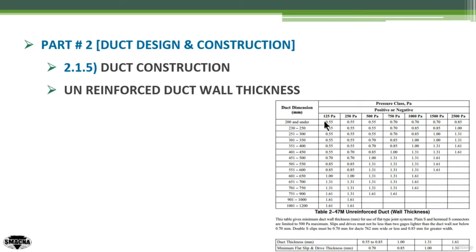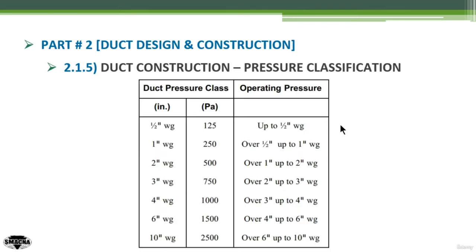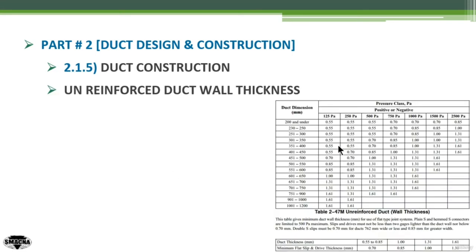The duct pressure classification depends on the external static pressure (ESP) of the fan. For example, a fan with 1.5 inches ESP gives a duct pressure classification of 2-inch water gauge, because 1.5 falls between 1 and 2 operating pressure. This is the second input.